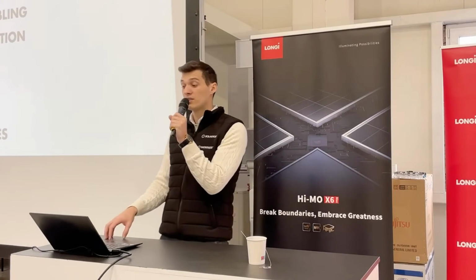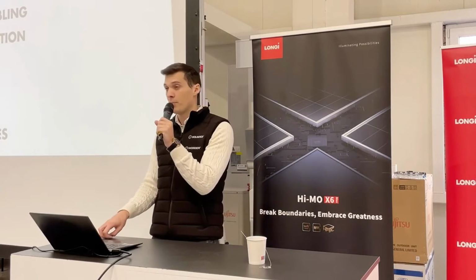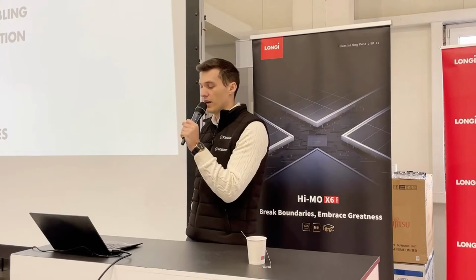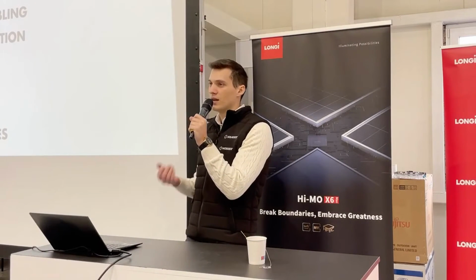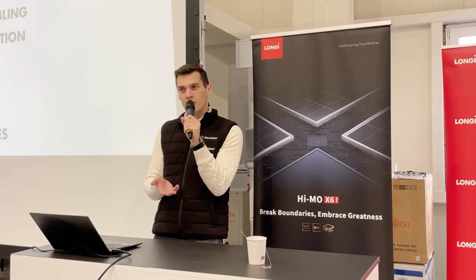W03 error code. Once you decide to change that and you press on the setting, it will have the pop-up window where it will ask you, are you sure you want to change this, because it could cause damage to the inverter. Please be calm, you can change it, it will not cause damage to the inverter, it will only make it work. But even if you are on the good setup of the phase order and you change it to the wrong one, it will still not damage the inverter, so please do not be worried about that. Also, there is a touch screen, which means that the customer could access the inverter that you don't want, because if the customer changes the settings and it will not work for some reason, it will make you extra work, and for no reason. Also, it can cause problems with the regulations.